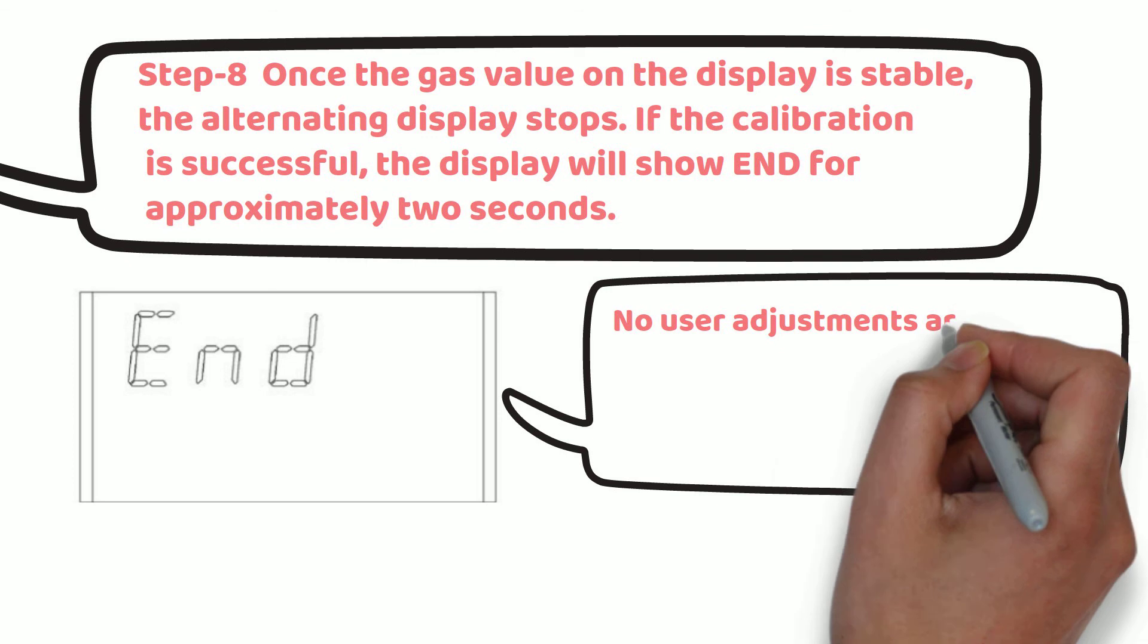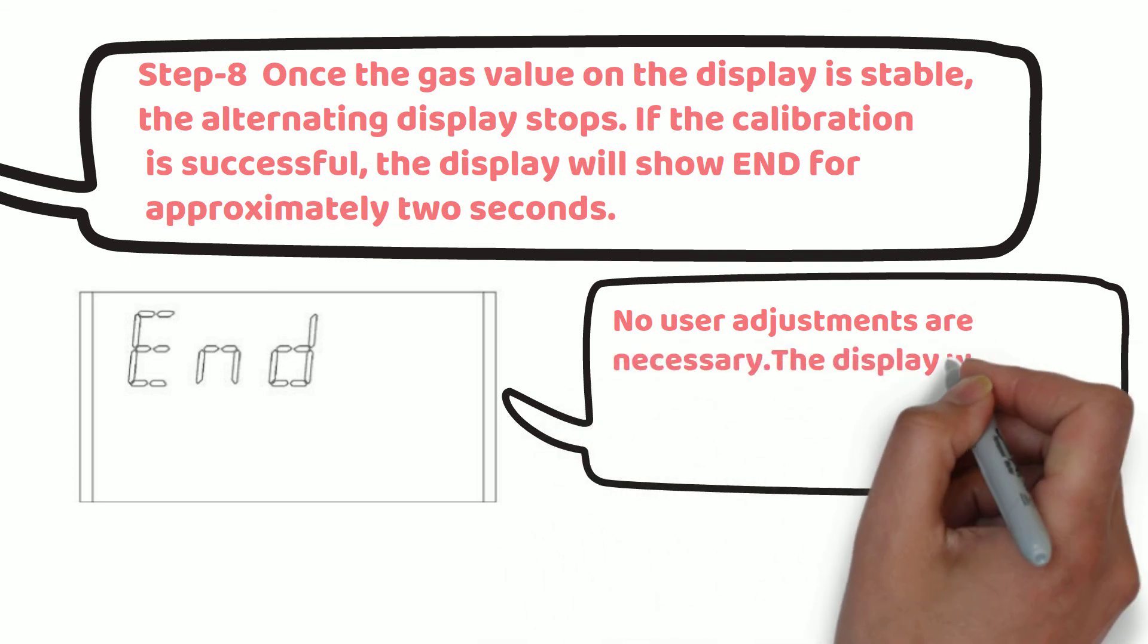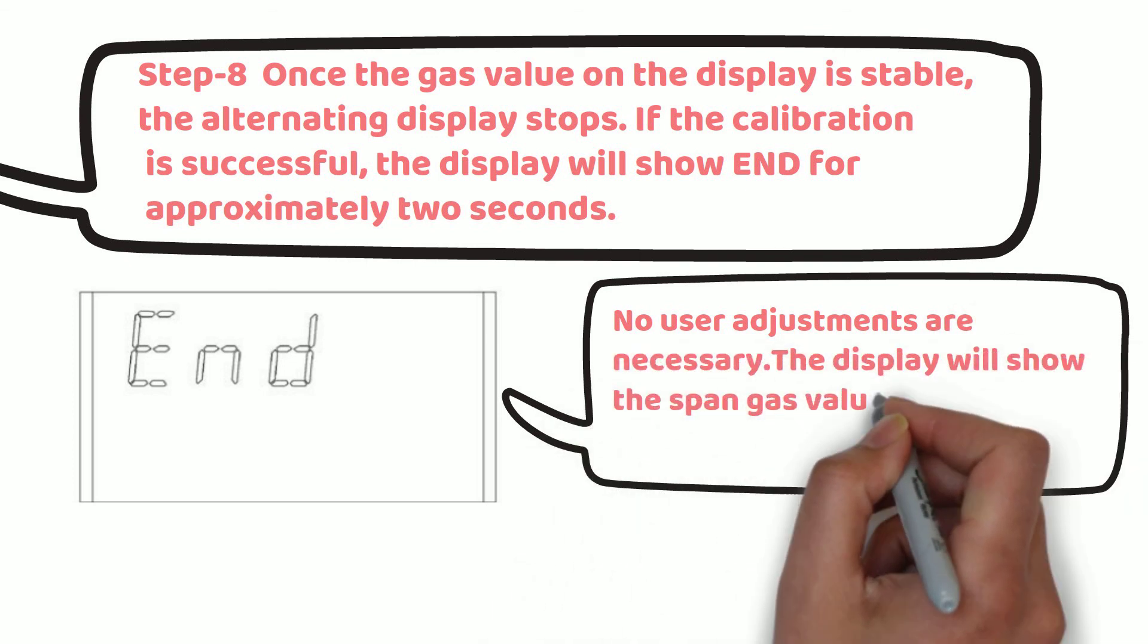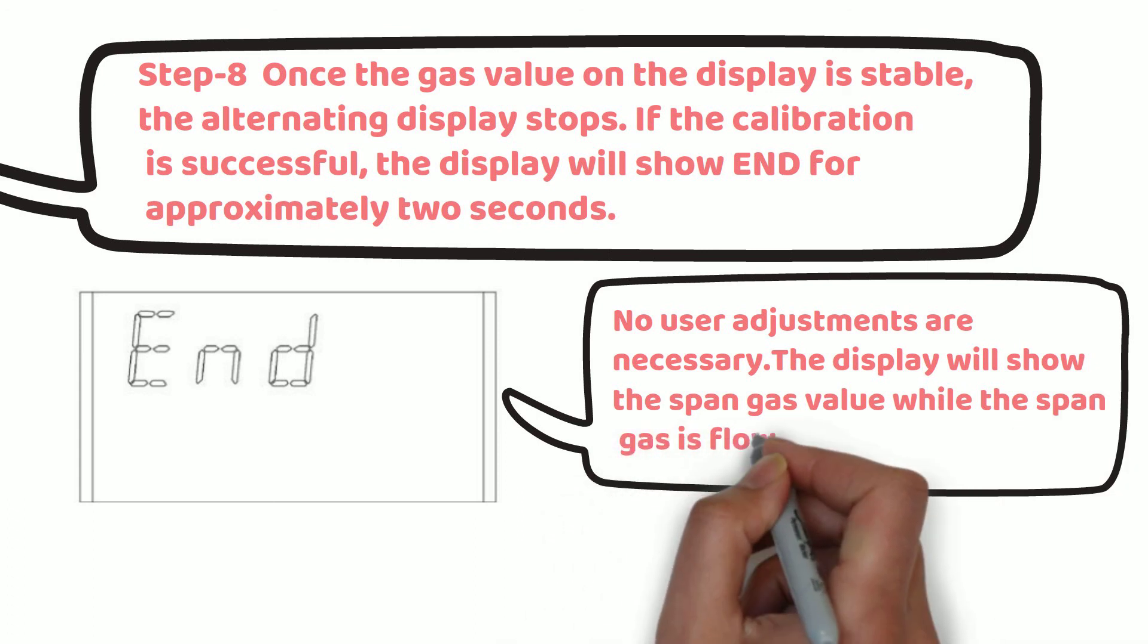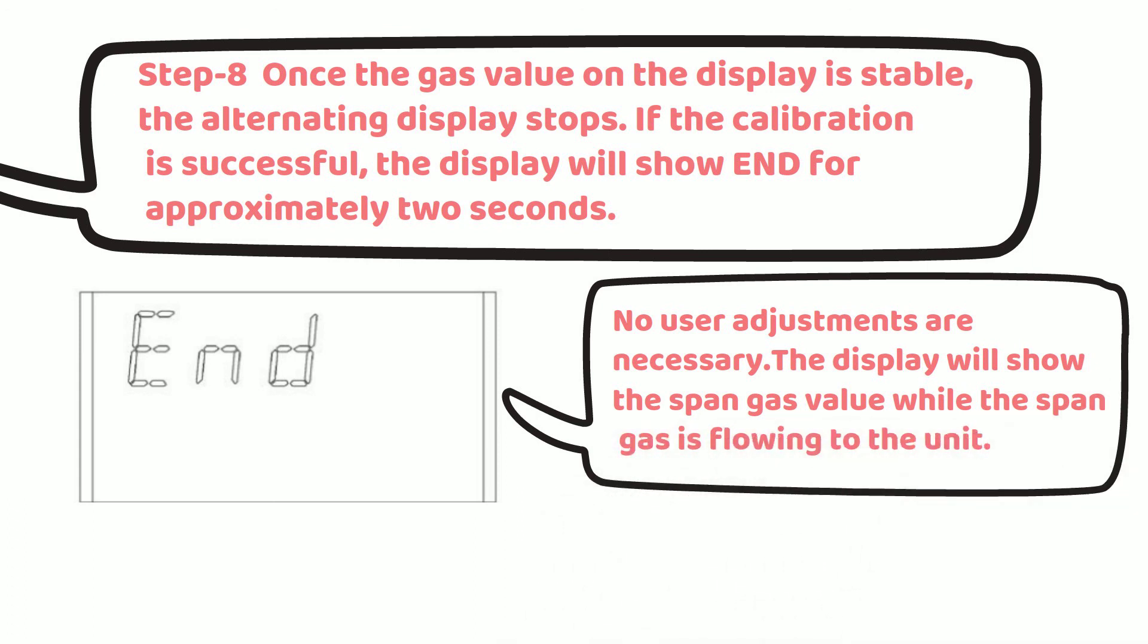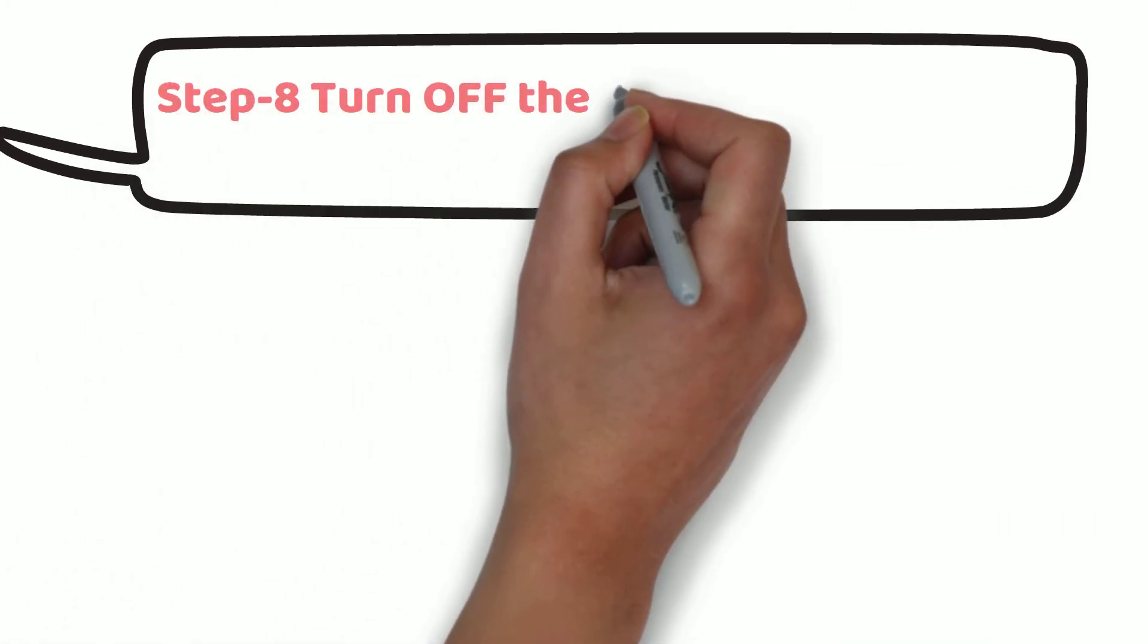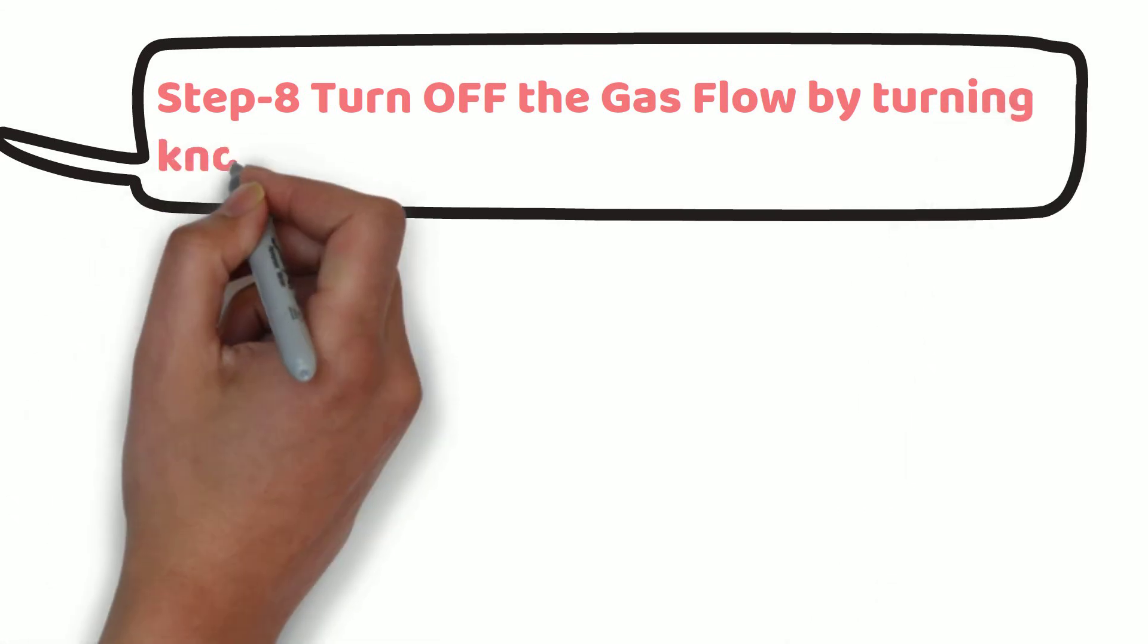Both zero and span calibration does not require any user adjustment. If the calibration is not successful, then cal fault message appears on the screen. In this case, you need to do recalibration. When end message appears on the screen, turn off the gas flow by turning knob on the flow regulator.